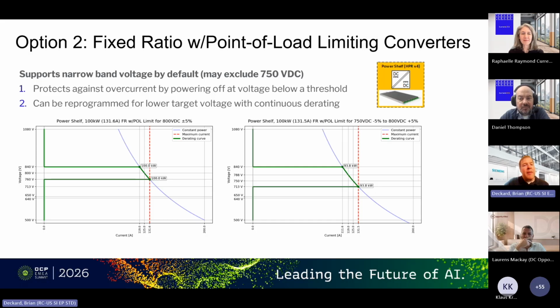One important point I'd highlight is that we've recently been able to enter a public input to the National Electric Code, whereby you can take an 800 volt converter and add a restricted setting to it, such that you could put two of those together and still be within a low voltage installation context. This is another important planning-ahead measure that helps ensure we're designing for sustainability and reusability of equipment into the future.